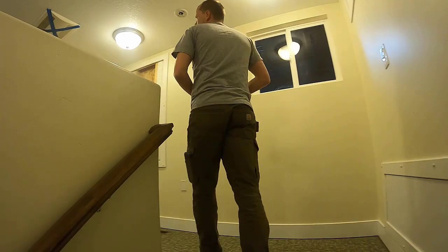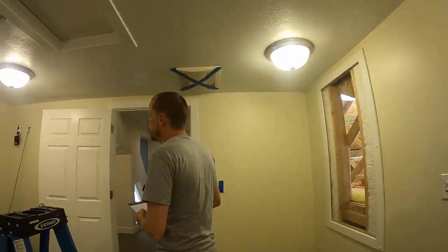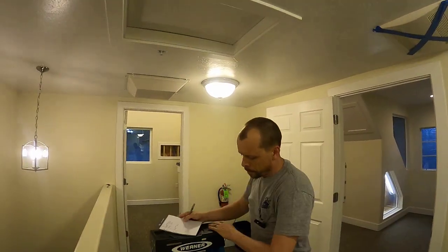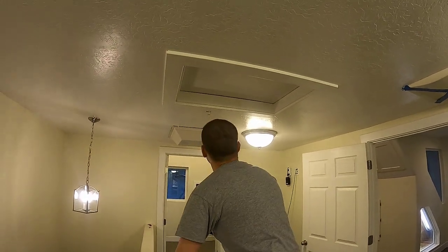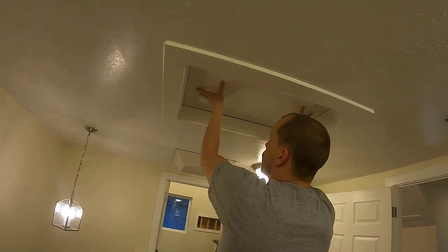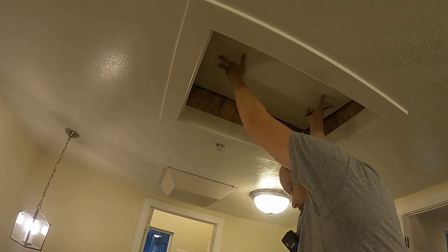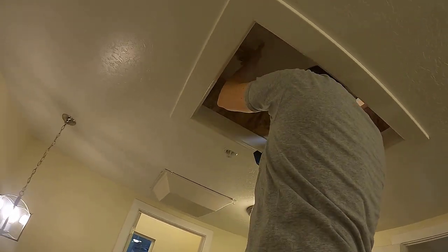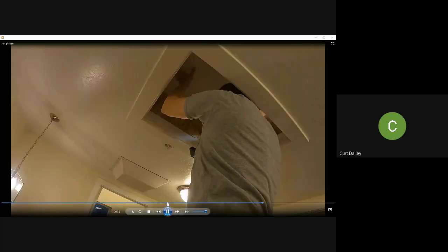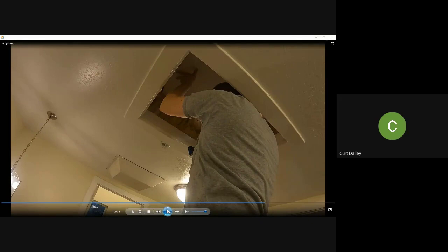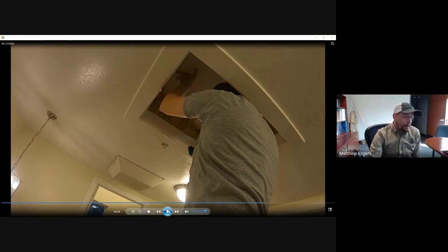So now I'm going to go open the door again between the zone that I'm testing and the house. Are there any questions at this point? Everybody following? At one time, they brought up that you could only open the door so much. How do you know when to open it so much? It's kind of touch and feel. Again, you need to get a pressure difference of at least 6 pascals.